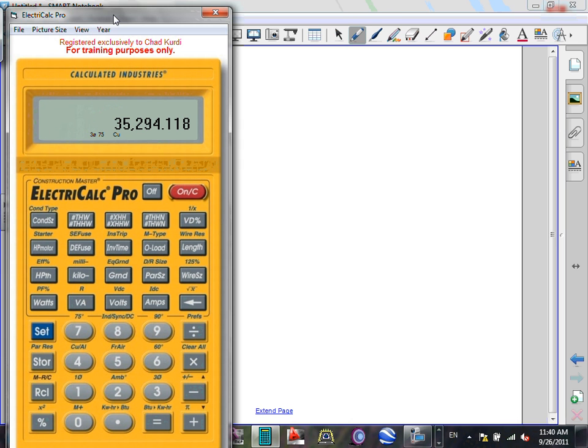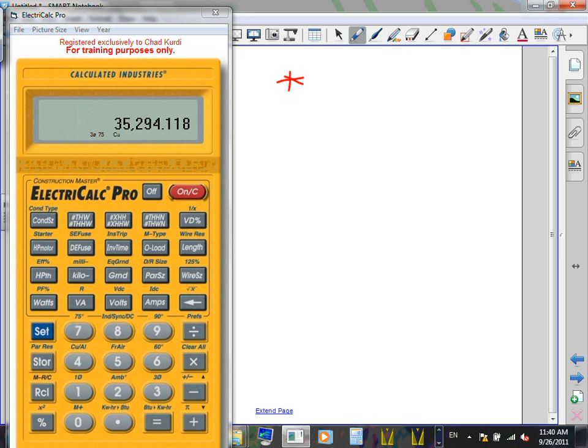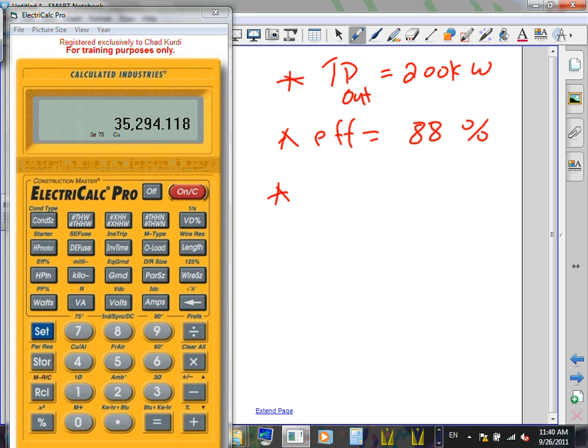I have a system, my system true power out - I'm giving you the true power out, 200 kW. And efficiency, the efficiency of this system is 88%. You guys have just done that. What are the input amps if the voltage is - I need I input, that's what I need. And if the voltage system is, the voltage equals 208 volt, and the system is 3 phase.